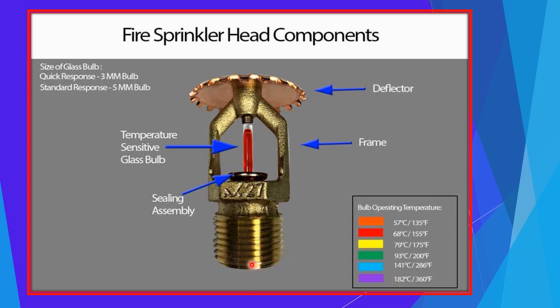centigrade. So the connection is done on the pipe, through which your water is coming, and this pressurizes the diaphragm, and the quartzoid bulb holds it in place, and no water is flowing. But once the temperature rises in the compartment, the liquid inside this temperature sensitive bulb will expand. The volumetric expansion will create a huge pressure, and the bulb will shatter. Once the bulb shatters, the diaphragm comes out, and the water starts flowing. This water will fall on the deflector, and in the form of a spray it will cover the area and extinguish the fire.